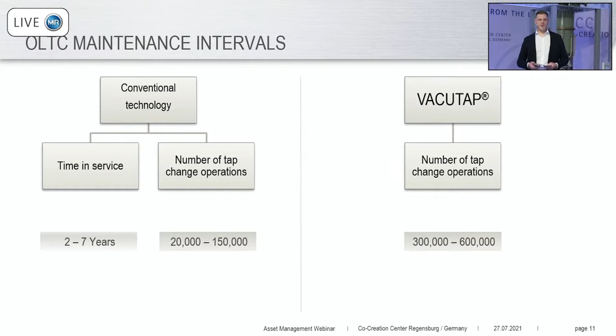When we now look at the VacuTap technology, we have just a number of tap change operations. And this is necessary between 300 and 600,000 tap change operations, which means we have no time-based interval. And for most network applications, that means that this tap changer type is maintenance-free. You can do some annual checks, for example, to be sure that your system is in safe operation.